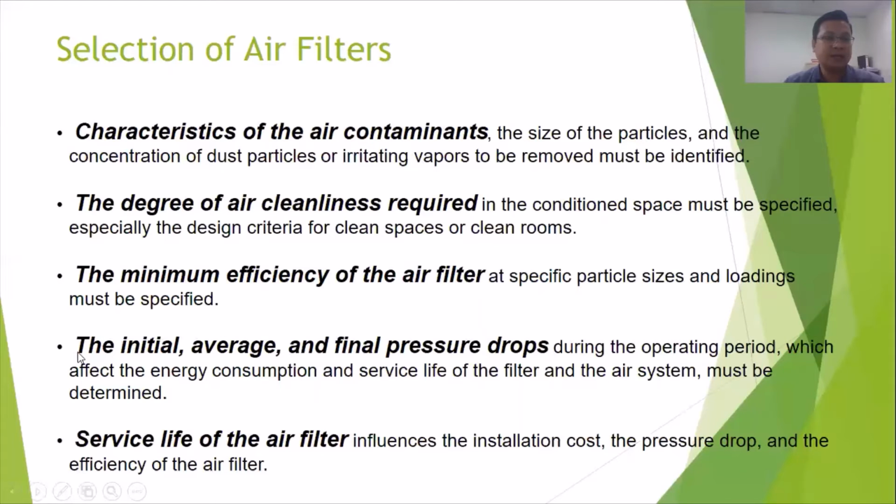And then the initial, average, and final pressure drop during the operating period, which affect the energy consumption and service life of the filter and the air system, must be determined. Service life of the air filter influences the installation cost, the pressure drop, and the efficiency of the air filter. So this should be considered when you try to select the air filter.